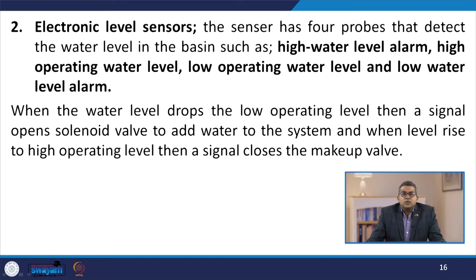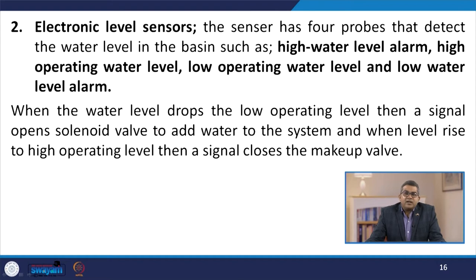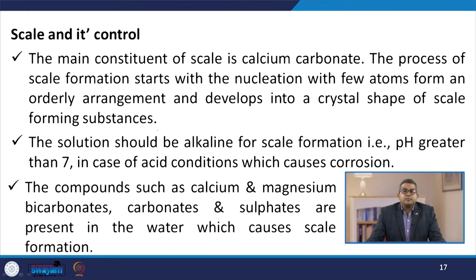When the water level drops to the low operating level, a signal opens a solenoid valve to add water to the system. When the level rises to the high operating level, a signal closes the makeup valve.